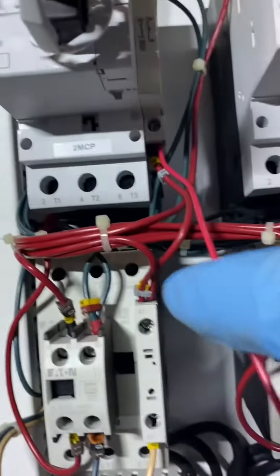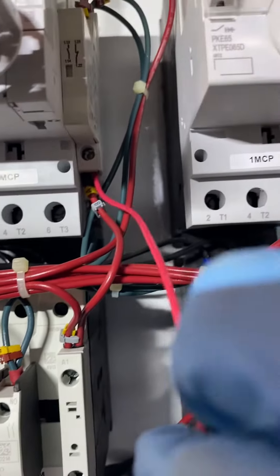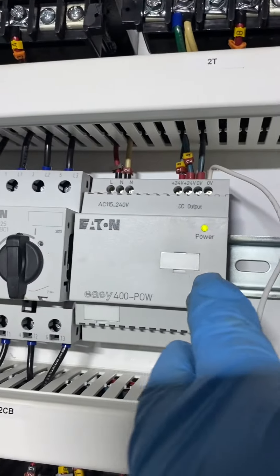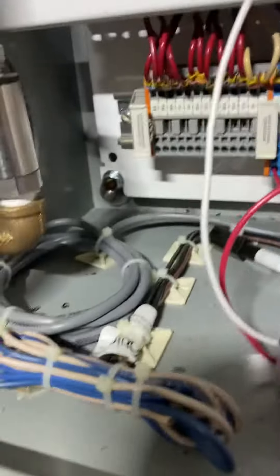All I need is to land on A1. As you can see, A1 already has two wires, so I install my wire there. A1 and A2 are for your power. A2, I'm taking it right out of the 0V because this is a 24V supply, and I've got my 24V right down there. So this will cycle on and off.